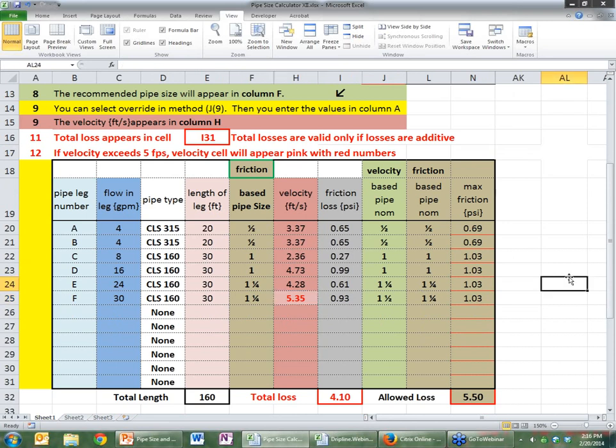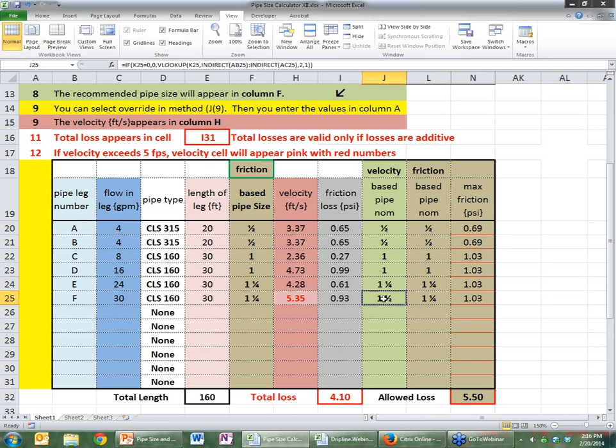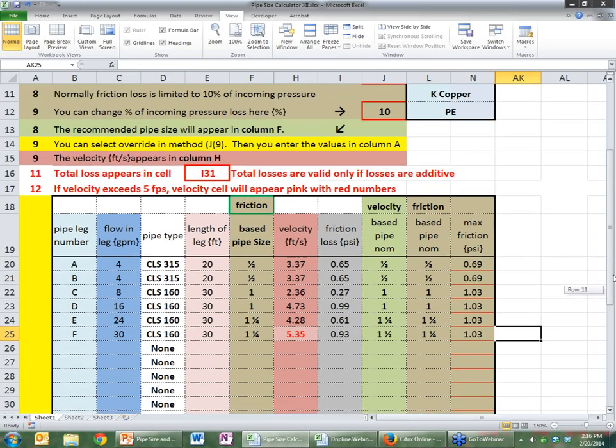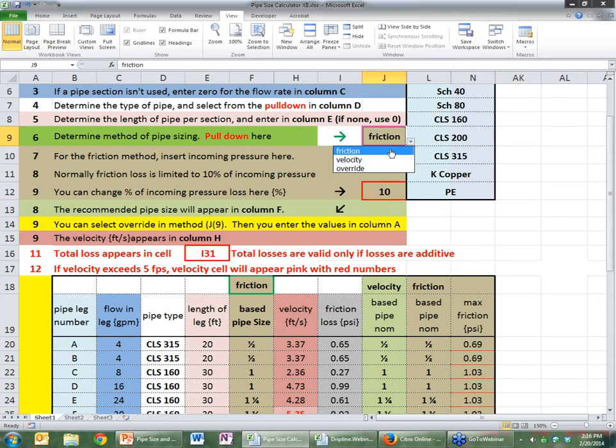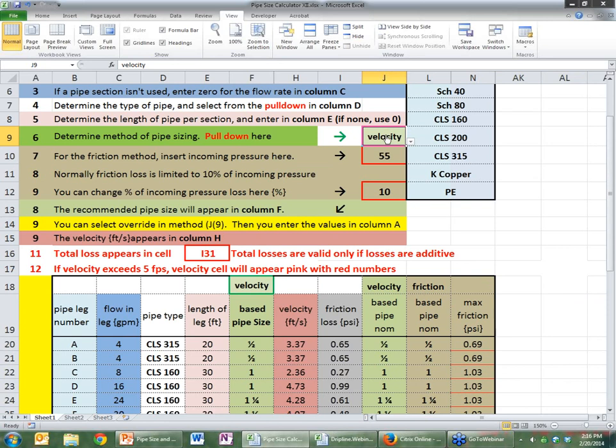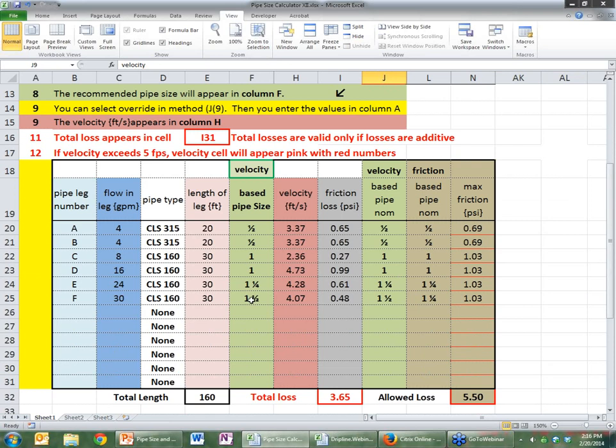And here are the results that you will see for those pipe sections that I showed you. And you'll see, for example, that this particular cell, which is H25, has changed lettering to red. And that indicates that the velocity is higher than the limit velocity, which is 5 feet per second. Now, the obvious solution to that is to pick a bigger pipe. Now, what you might notice over here, if it were velocity-based pipe, the nominal size would be one and a half in that particular size. So you see that that would resolve the problem. Let's go back up here and change from friction to velocity.